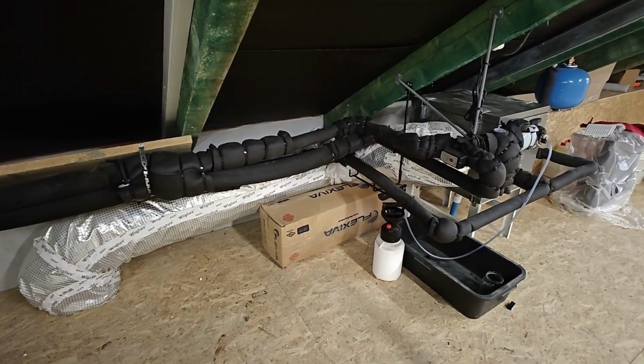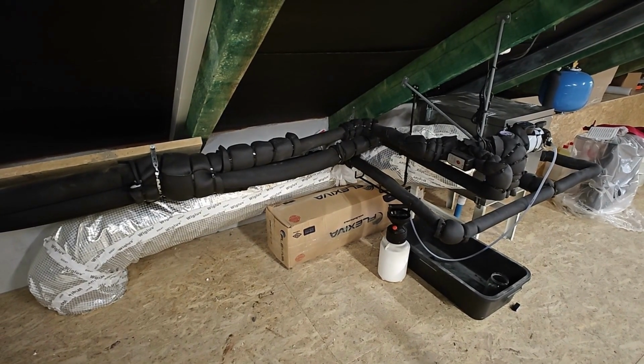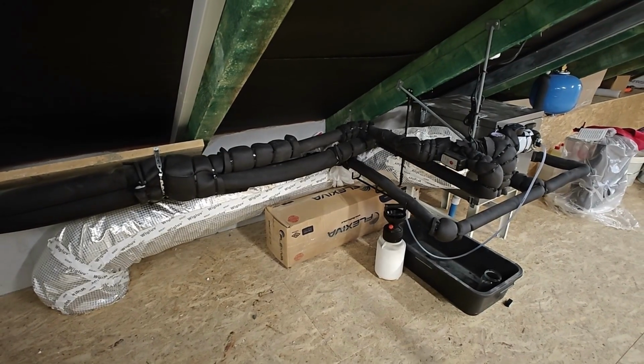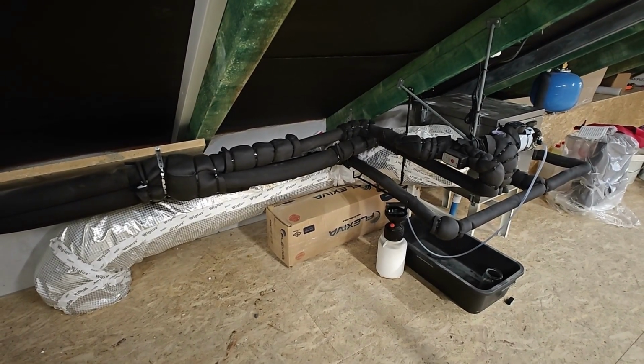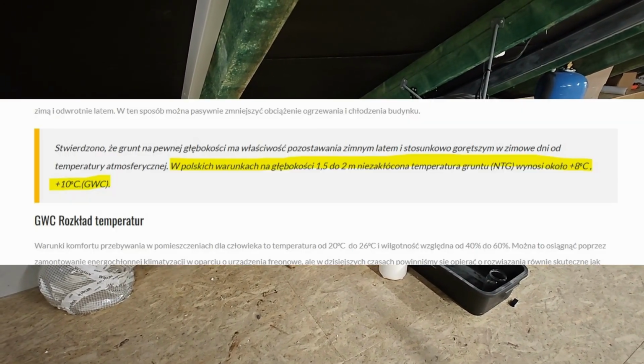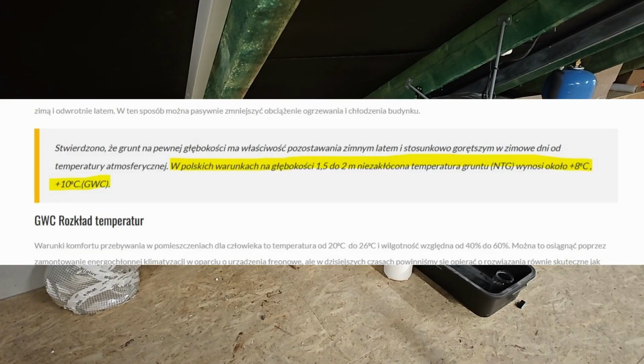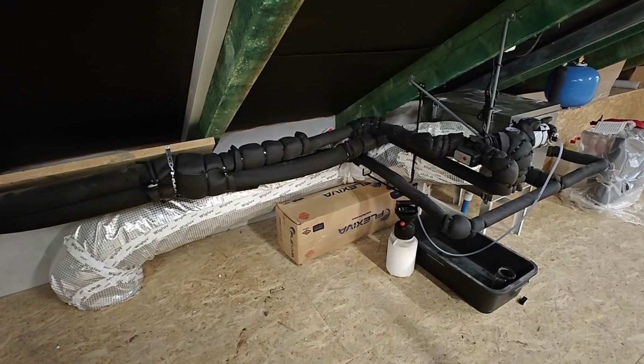When discussing this part of the system, it's worth noting the information available online regarding ground temperatures at such a depth. It's often said that the temperature at such a depth is constant, ranging from 8 to 10 degrees Celsius. I believe this is untrue.